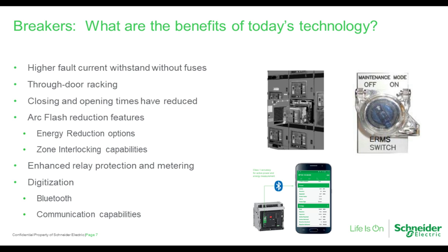We'll start off with breakers. Breakers, what are the benefits of today's technology? Well, with new low voltage breakers, higher fault current withstand without fuses, through door racking. And with through door racking, a lot of new manufacturers now have also remote racking for their breakers, which also puts the worker away from a risk of racking out breakers where an arc incident can occur.